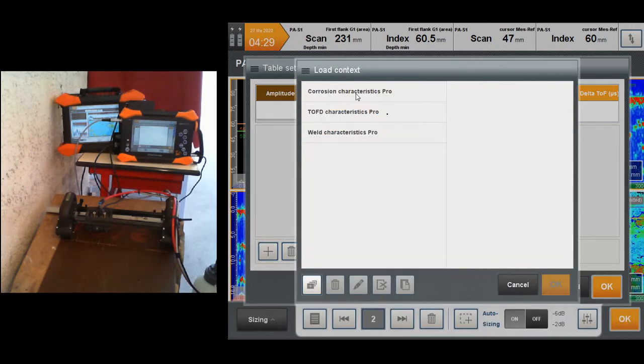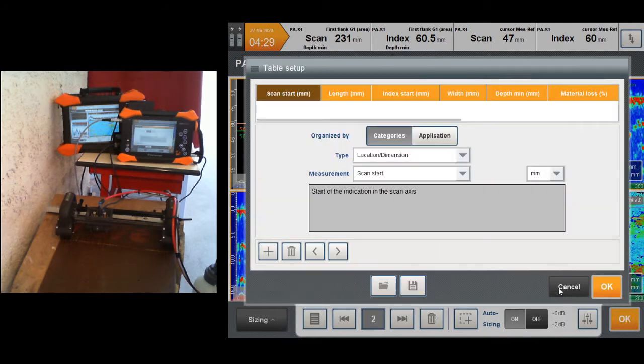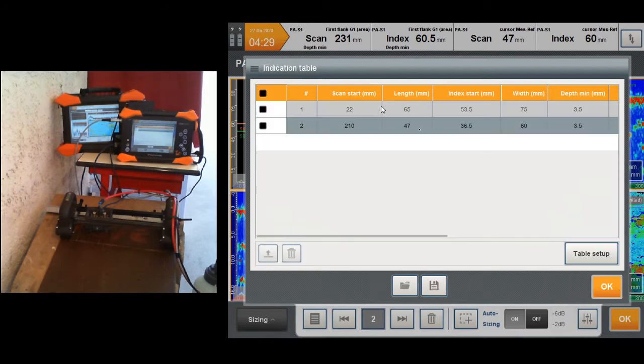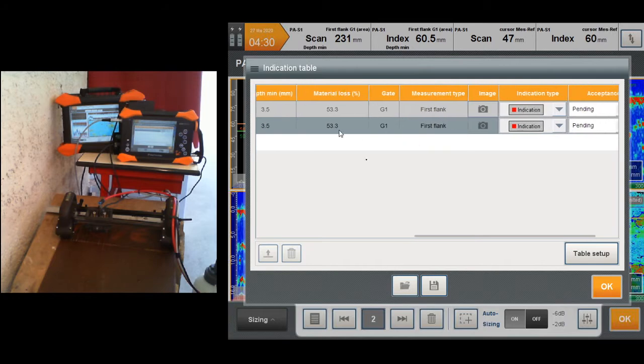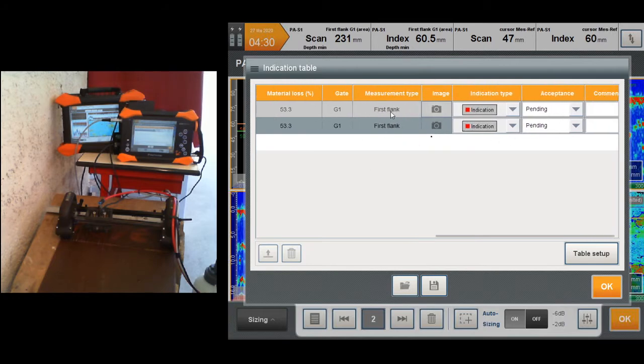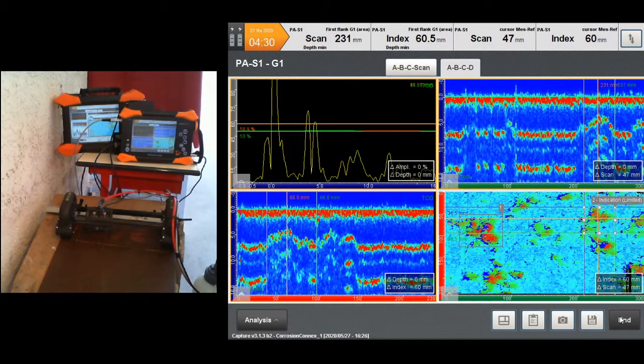I can load a pre-existing indication table, in which I have for each area where the area starts, its length, on scan and index axis, what is the minimum depth, and then the corresponding material loss. It has been detected on first flank in gate 1, and I can attach my screenshot to G1, and maybe I can consider both indications need to be rejected and press OK.